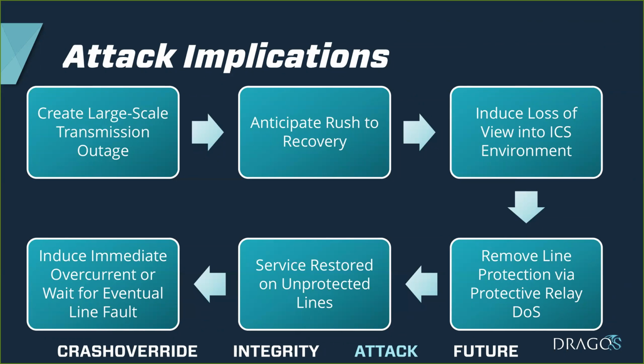So any subsequent faults, due to either regular anomalous conditions in the power environment, bad weather, etc., produces a situation that would normally be mitigated by the digital protective relays, but instead cascades onto the transmission site itself, resulting in physical wear and tear and possible damage.